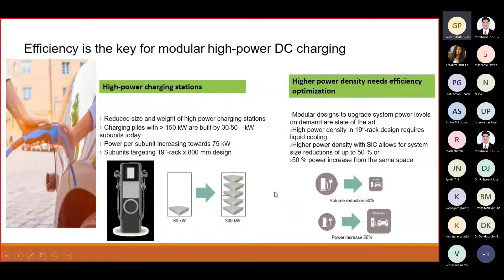On the charging side, as I mentioned, we need two stages: one should be AC to DC, and the other DC to DC. Sorry, it should be DC to AC for the second stage, DC to DC stage. In the primary stage, AC to DC, there are three kinds of topologies we have at the moment in the market. For most 50 kilowatt systems we use a Vienna rectifier below 50 kilowatts, where the central switches have power factor correction control, and the remaining voltage you get from there. But this is not preferable for high power, so then your active front end comes into picture.